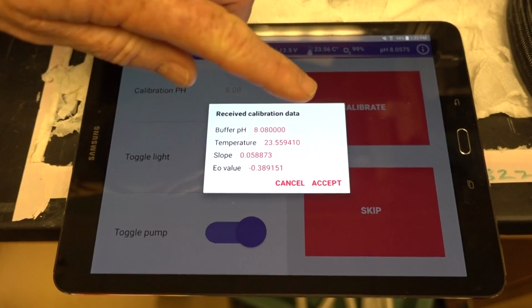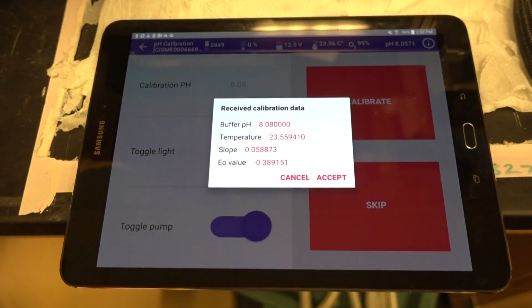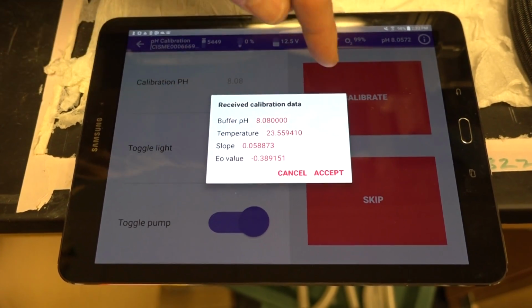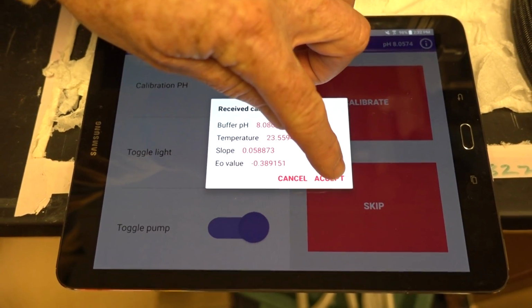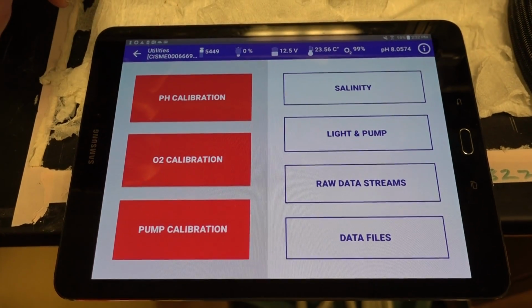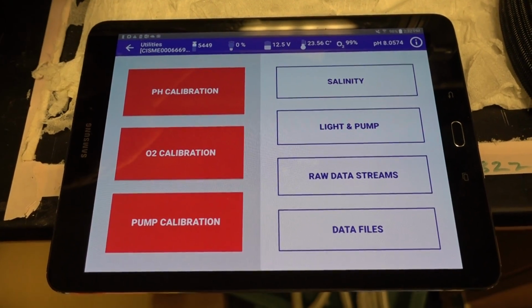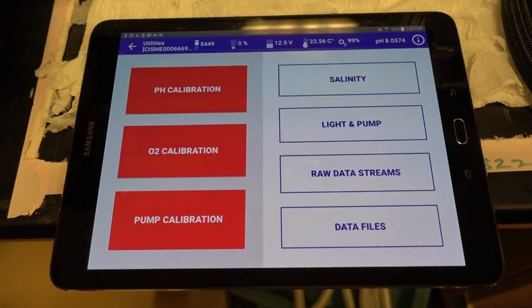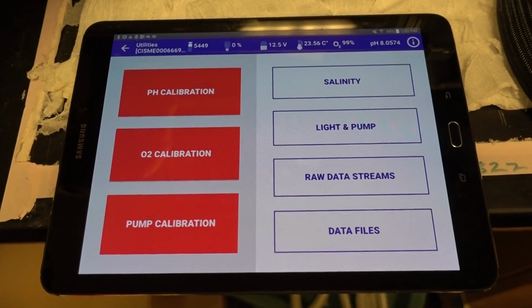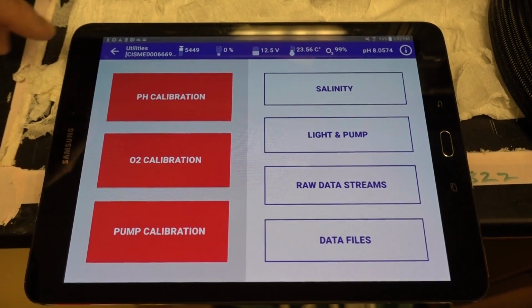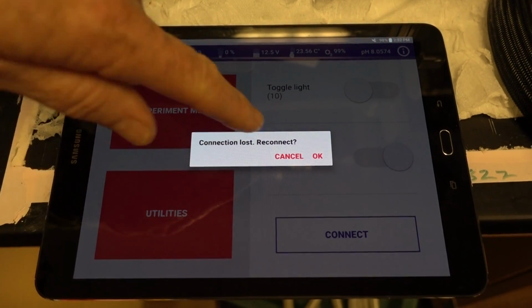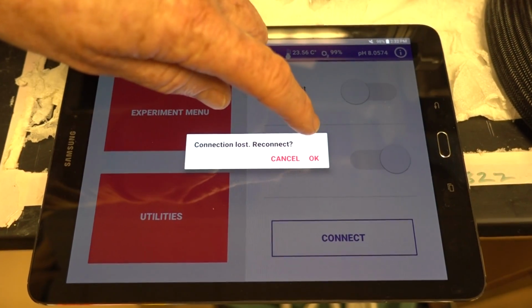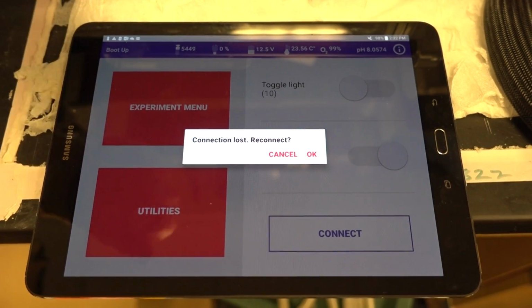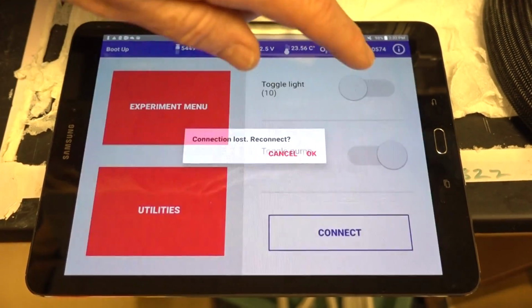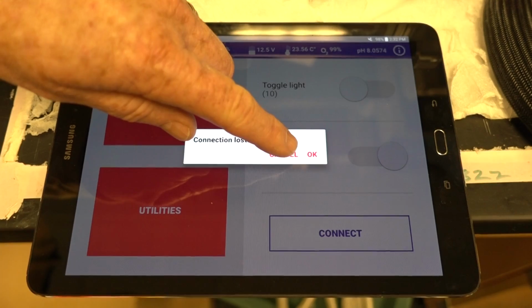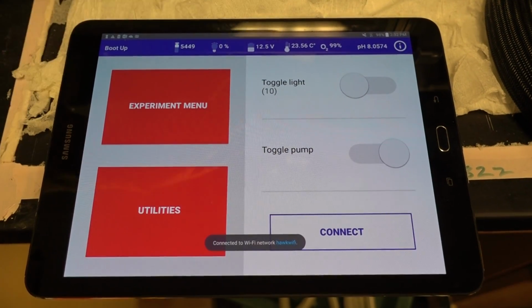Again, it comes up with a screen. We can either cancel, in which we will retain our old calibration factors, or accept, and the new ones will be written to memory. With the pH calibration, when you accept, it requires a reboot of the system, and so the system will automatically reboot now and go through its reboot process, in which case it will have been disconnected from its Wi-Fi and you will have to reconnect. It will take a moment before you'll be able to reconnect. So I'm going to hit cancel here and wait for a minute for everything to boot up.